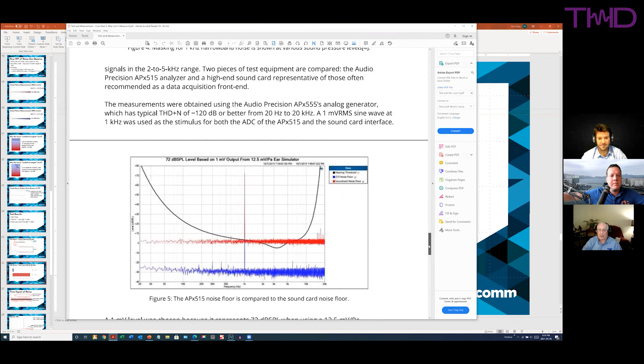This, by the way, is a sound card that an audio test equipment manufacturer recommends for electroacoustic measurements. So the blue curve is the noise floor with an electrical signal representative of 72 dB sound pressure level. This signal is 1 millivolt RMS based upon a microphone with 12.5 millivolts per Pascal. So what's so magical about this particular microphone sensitivity? That's the common microphone sensitivity in the microphones used in the ear couplers for headphone test fixtures. So what you're seeing here is the threshold of hearing. It's actually below the noise floor of this particular sound card.